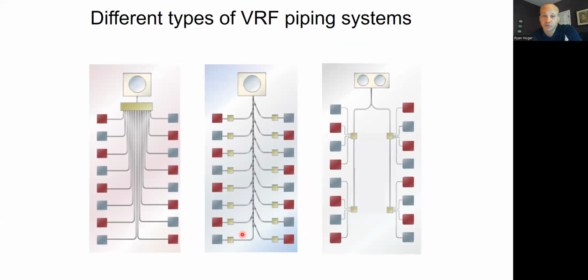That's not the only way to do it, right? The way I just described was this way or this way, right? So I got this piping running down the middle of the building. It branches off. Each one goes to a switching box and to its zone, or it goes to a switching box and into multiple zones. The other way to do it, and I think only two manufacturers do it this way, is you have a two-pipe mixed flow system from the outdoor unit to a distribution box, or a branch controller, one manufacturer calls it. And you have in that one pipe both a liquid and a gas together. And this box's job is to separate all of that out. So it's two pipes from here to this box. And then each zone has two pipes home running back to it.